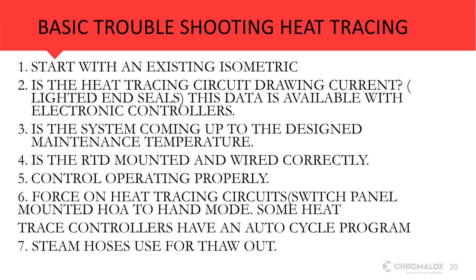So let's talk about the heat tracing side of troubleshooting. Again, I like to start with that isometric, right? Let's look at that. Is the heat tracing circuit drawing the current that it's supposed to? Do I have a lighted end seal that I can look at and see that I have continuity through the line? If the heat tracing circuit's drawing current, you may have a controller that gives you that information. If not, you may have to go with a meter and do some tests to see if you have the proper current.